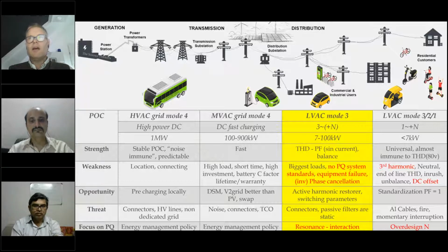I think it's also very difficult to do, because not only do the chargers have their own switching frequency, but in the building you also have a copy machine, LED drivers, and EMI filtering. The EMI filtering might not only filter itself, but the EMI filter could also filter the grid. And when the EV chargers are putting in terrible harmonics, the EMI filters from the rest of the installation will eat them.